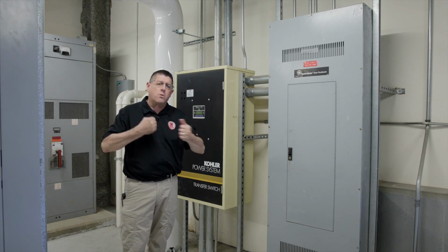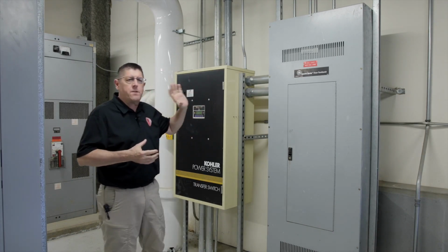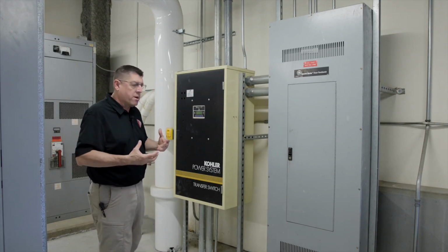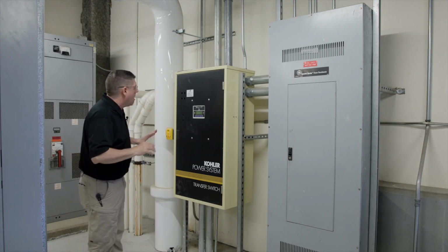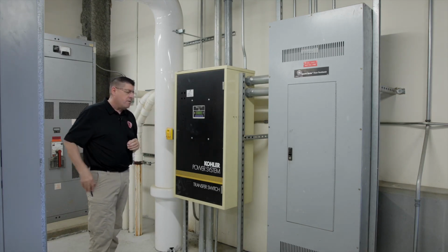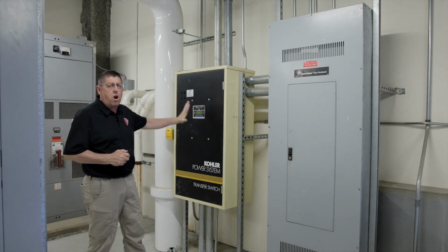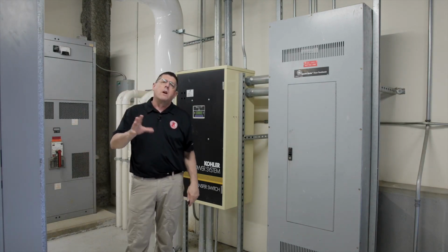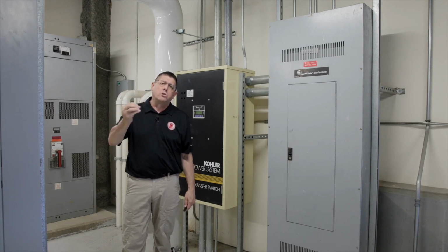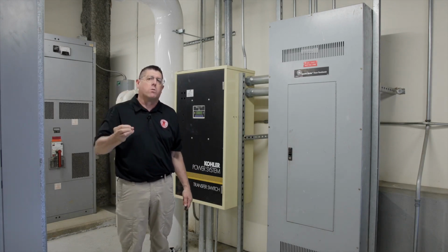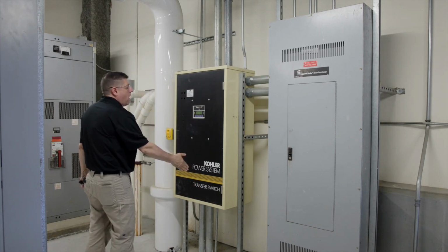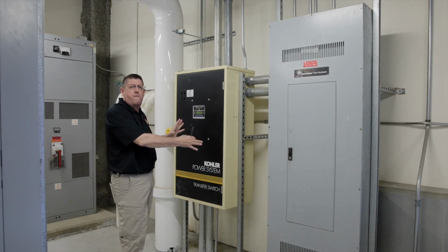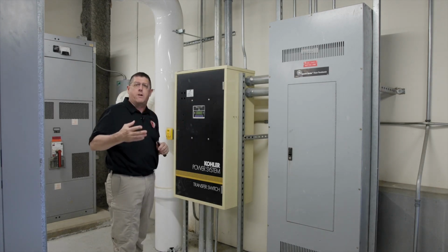As I migrate from the outside to the inside, now, these don't have to be directly continuous. They could have the generator well offset and then put in through conduit the electric through the raceways to service this. But this switch that we have right here, this is our transfer switch. This is the heart of the unit. This is what is interconnected to the main electric coming into this building. And as soon as we have a pronounced power loss, it will shut off the main power from the grid and allow the generator to fire up. And now it's on generator power.